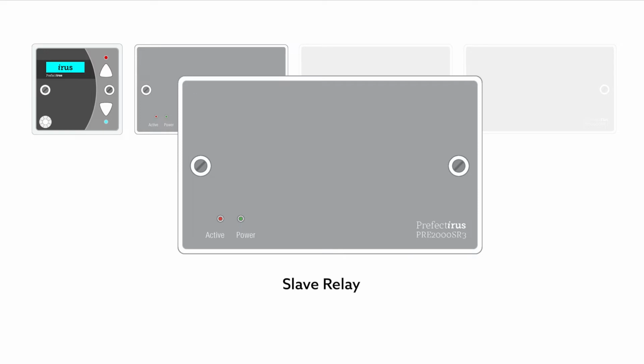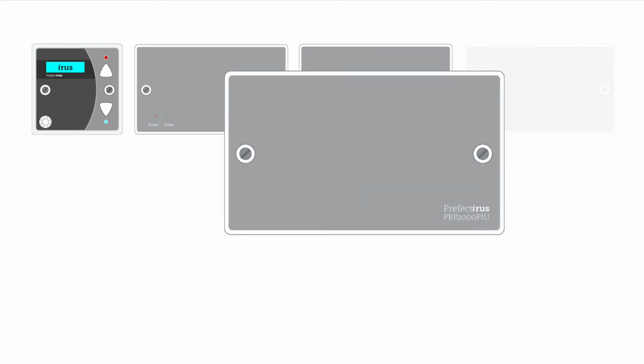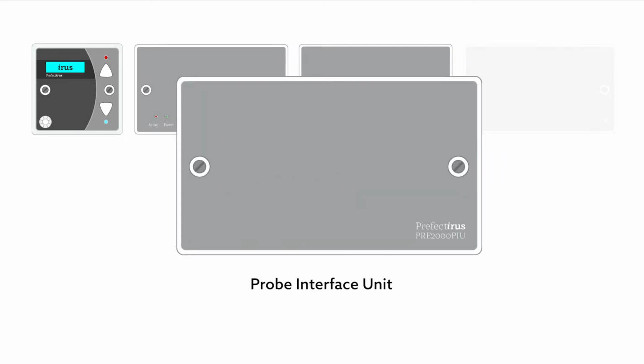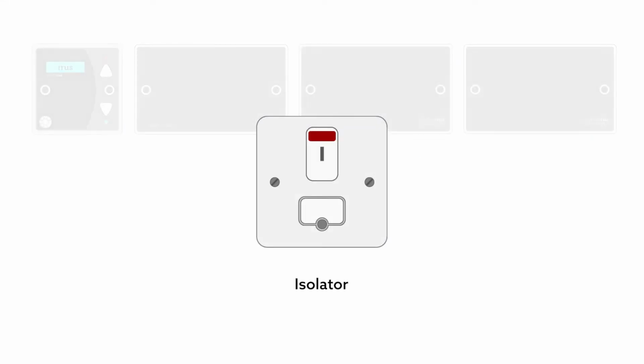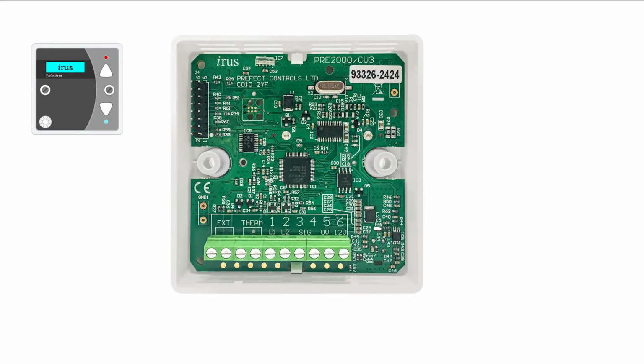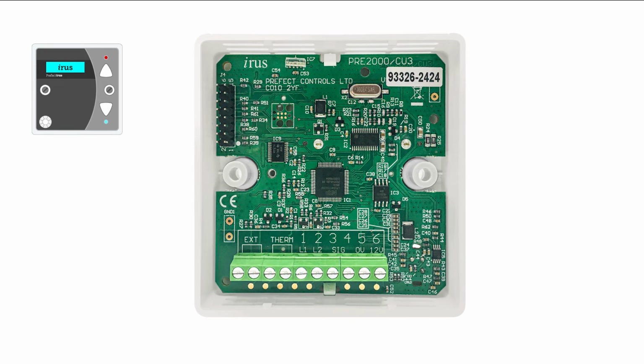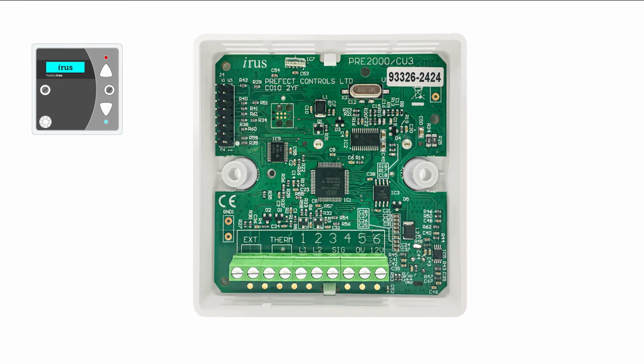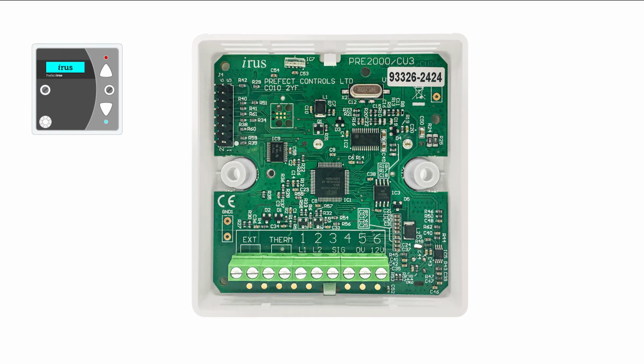The slave relay is a second relay output, and when used in conjunction with the power unit, provides the control unit with the use of 2 16 amp relays for switching twin-element hot water tanks. The probe interface unit is a link between the tank temperature probes and the control unit. For maintenance or replacement of components, double-pole switches are essential for isolating the elements, power units, slave relay, and control unit. The control unit is an electrostatic sensitive device, and therefore care should be taken not to touch the printed circuit board. Throughout installation, ensure all terminals are secure, but do not over-tighten.